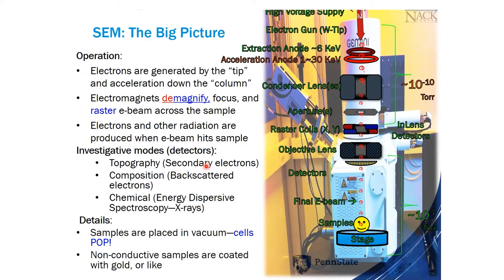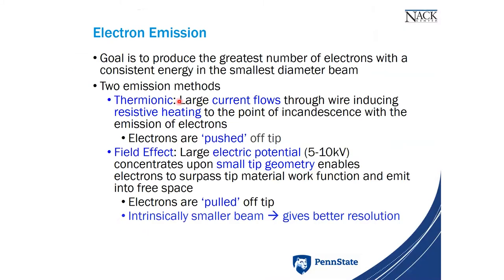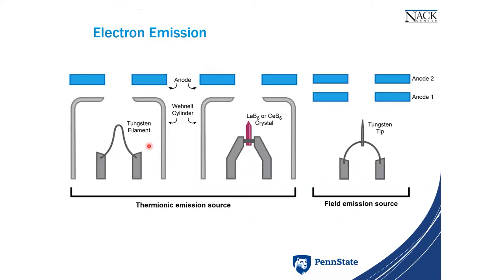First, we need to produce an electron beam to investigate the sample. All the E's represent electrons, and everything comes from the top. We start with an electron gun — an electron source, just like a light source for an optical microscope. To get an electron beam, we need something rich with electrons: metals. There are two main ways to release electrons from metals: thermionic emission, using heat, and field emission, using an applied electric field.